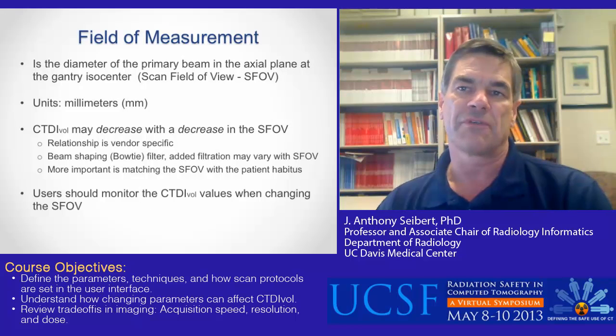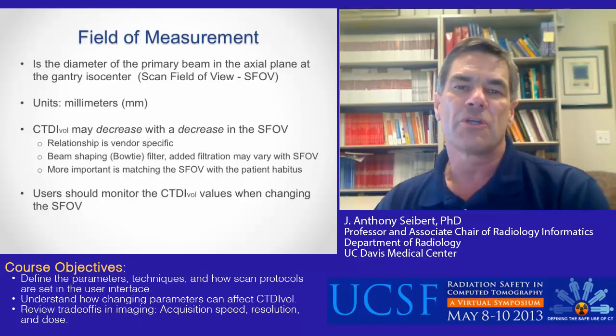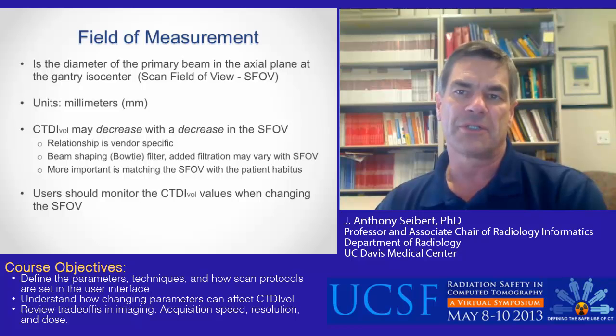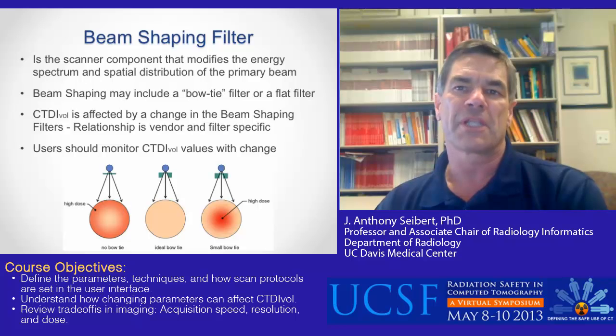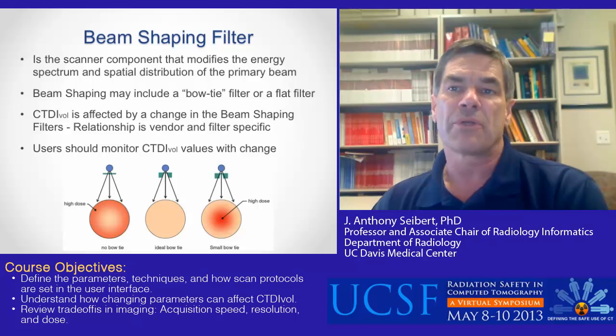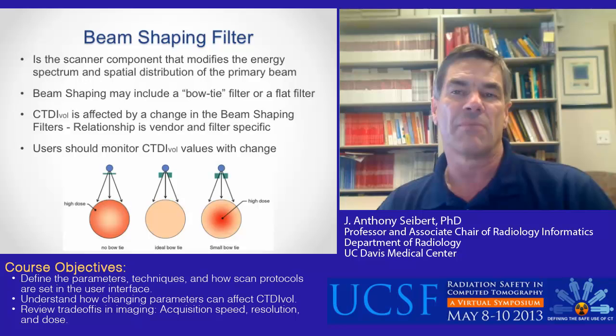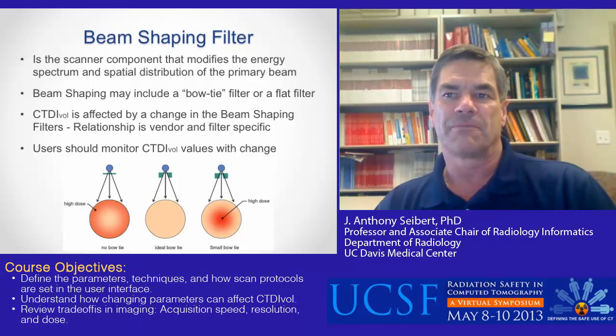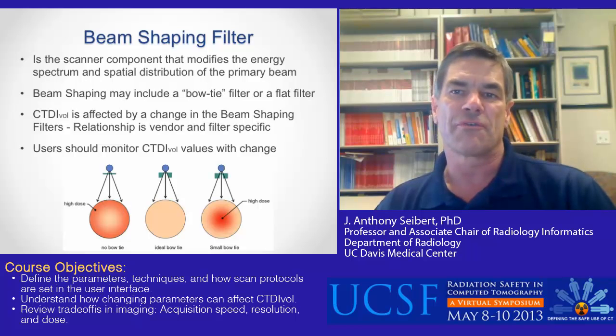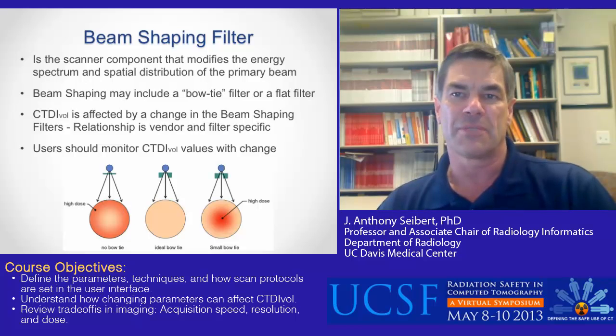The field of measurement, also known as the scan field of view, is typically expressed in millimeters. There may be a decrease in the CTDI vol with a decrease in the scan field of view, so it is important to monitor CTDI vol values when changing the scan field of view. Usually determined by the selection of the scan field of view, the beam shaping filter—which may include a flat filter, a bowtie filter, or both—modifies the spectrum and spatial distribution to match the characteristics of the patient. Ideally, the bowtie filter creates a uniform distribution of dose throughout the scan volume. No bowtie filter results in dose deposition near the surface, while a bowtie filter meant for a smaller diameter results in higher dose deposited in the center of the volume.